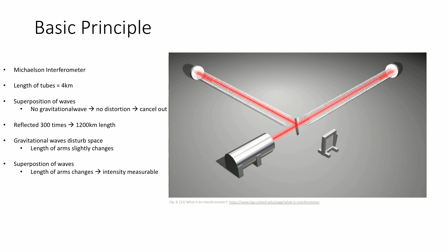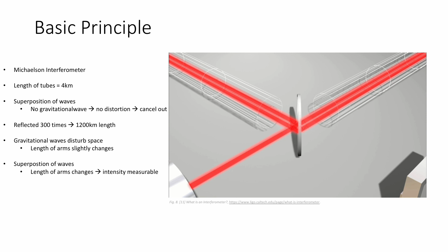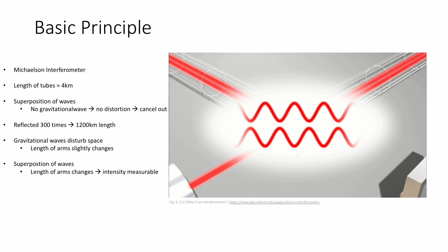The mirrors there are cooled down just to reduce the thermal distortion. Here we see when the laser beams are coming back, the setup is built in a way that these reflected light beams exactly cancel each other out. So if there is no distortion of the beam, they cancel out and the detector won't measure anything. Furthermore, the laser beams are reflected back and forth for about 300 times, which increases the length of each arm to about 1,200 kilometers.